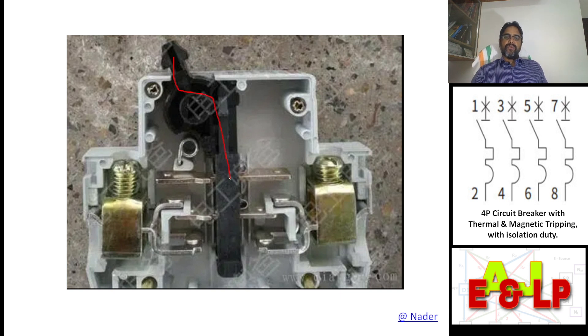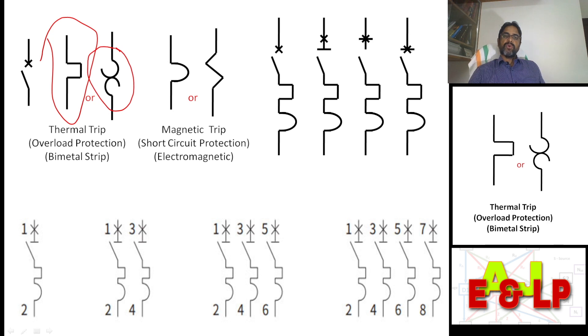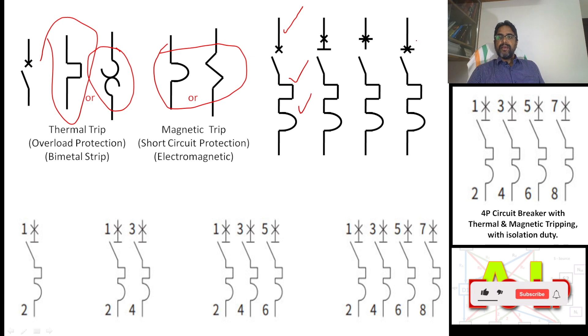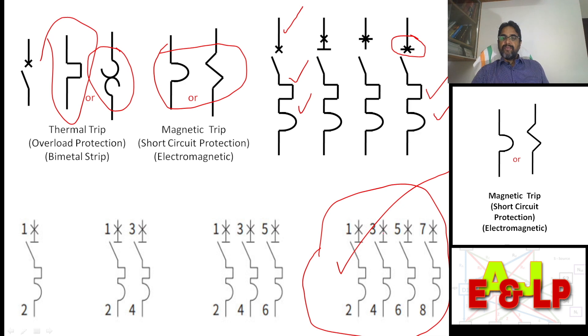Here is the cross-section of an isolator — there is no electromagnetic tripping or thermal tripping. Without any such protection it is simply an isolator. This symbol represents thermal trip and this one shows magnetic trip. So this one is a circuit breaker without isolation duty having both trippings. The last one is a circuit breaker with isolation duty and having both trippings. And a four-pole circuit breaker having isolation duty and both trippings — that is the meaning.